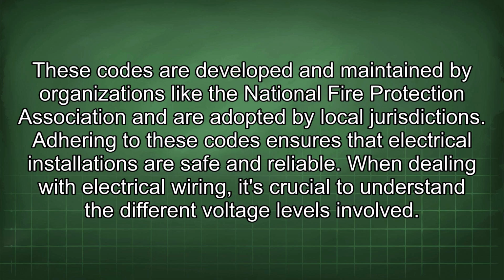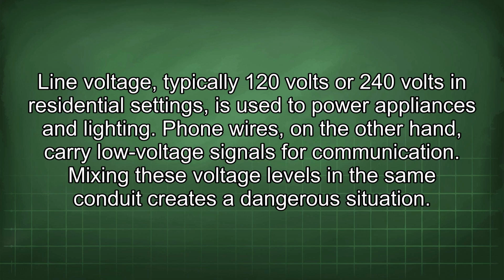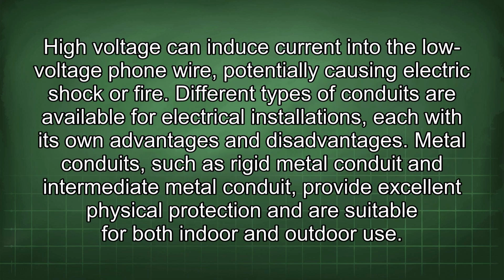When dealing with electrical wiring, it's crucial to understand the different voltage levels involved. Line voltage, typically 120 volts or 240 volts in residential settings, is used to power appliances and lighting. Phone wires, on the other hand, carry low voltage signals for communication. Mixing these voltage levels in the same conduit creates a dangerous situation. High voltage can induce current into the low voltage phone wire, potentially causing electric shock or fire.